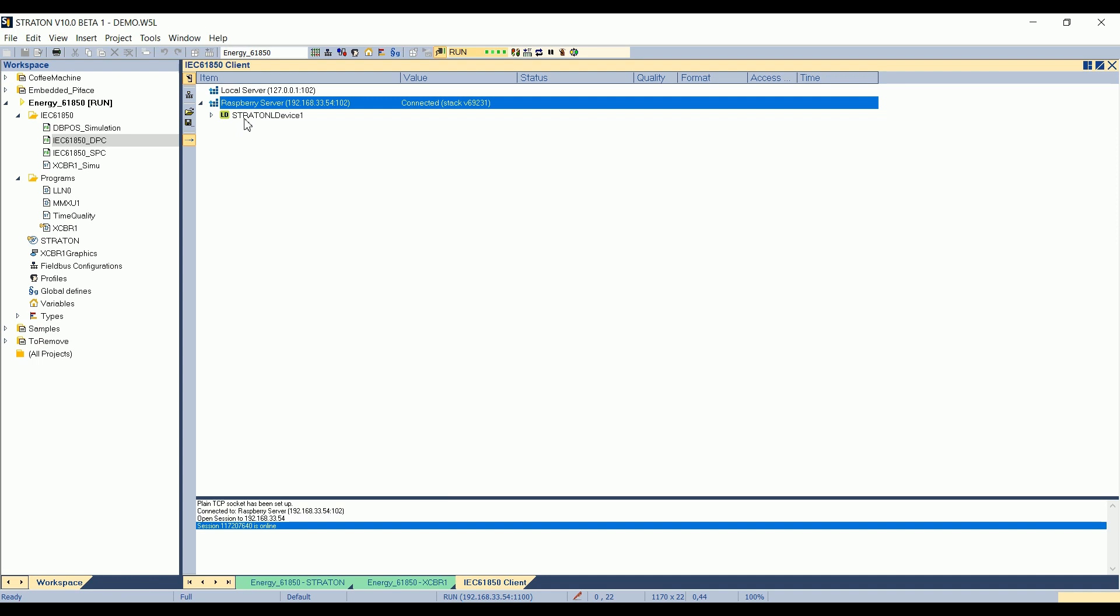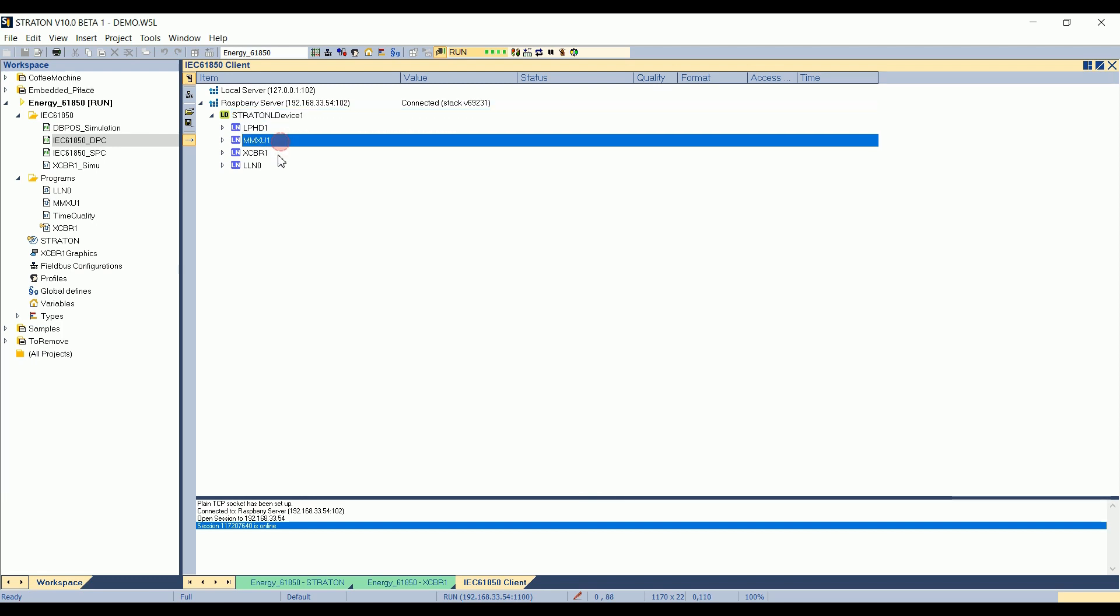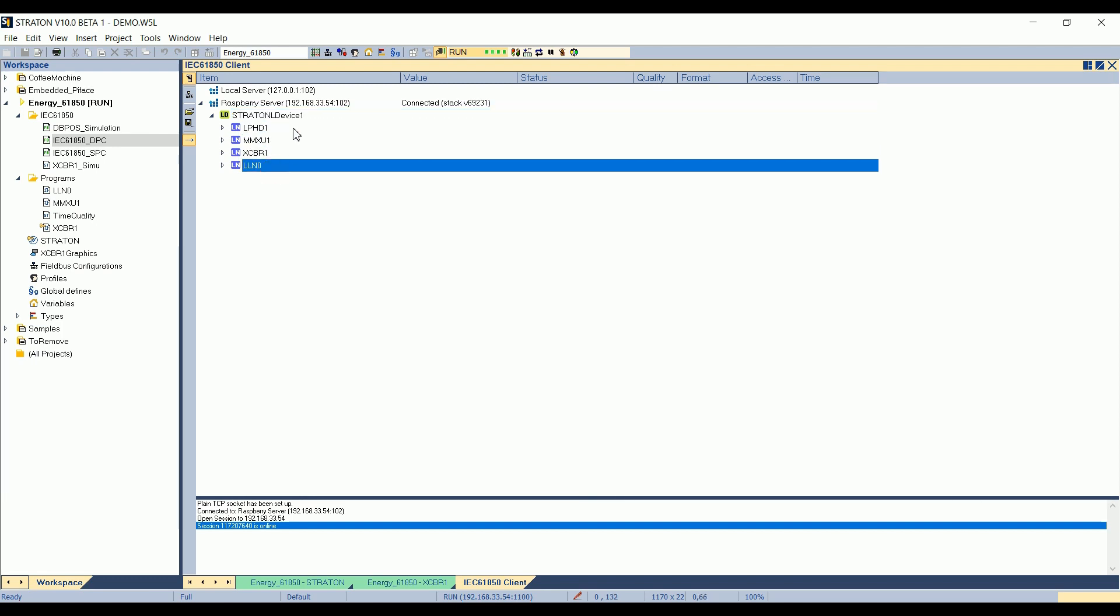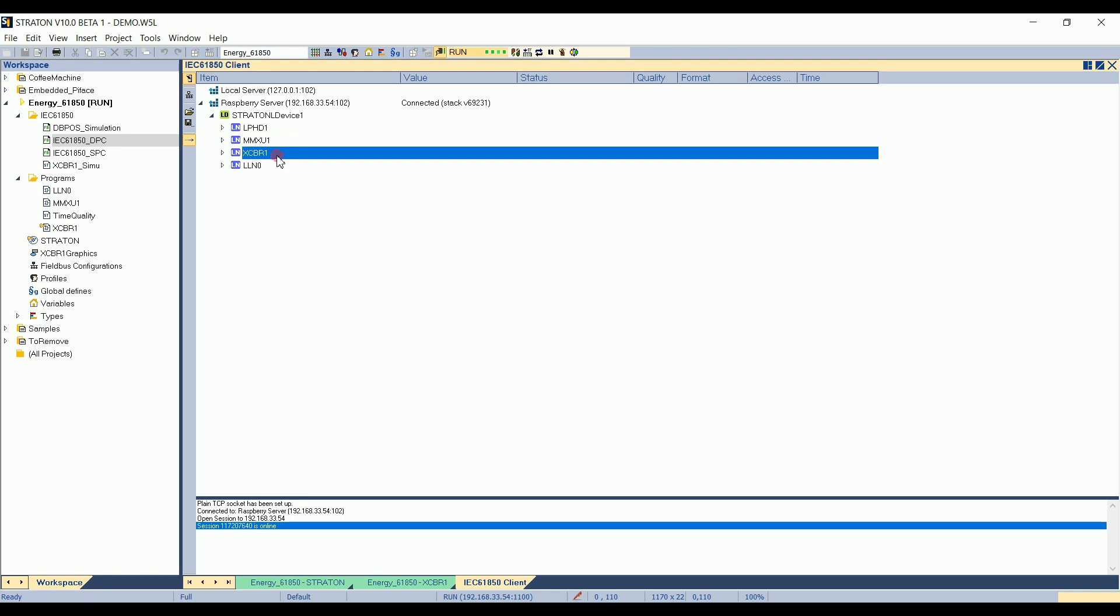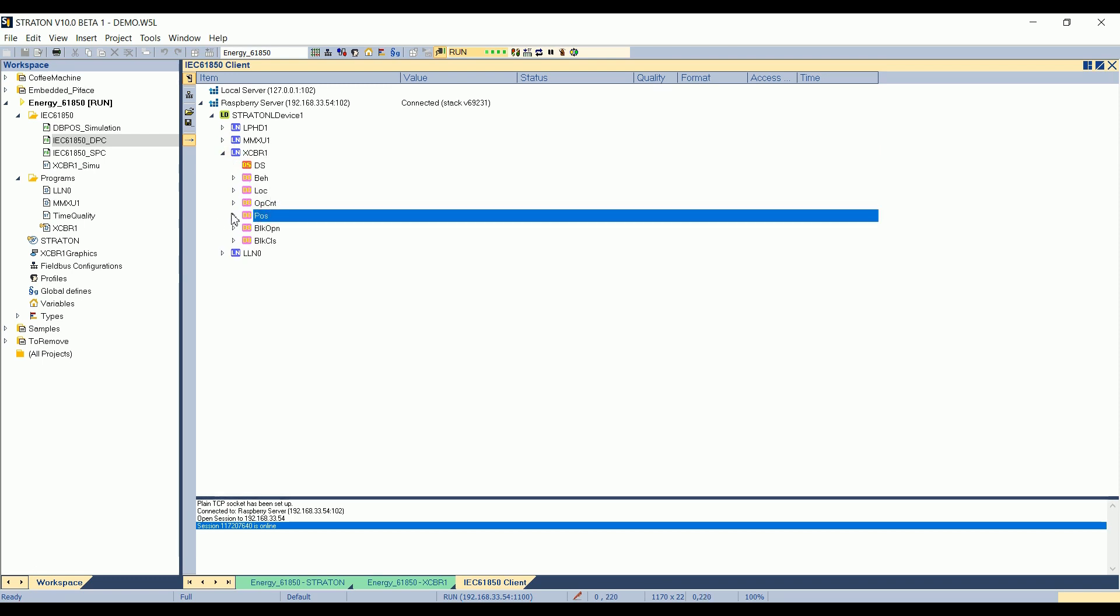It connects to the logical device, so to the Raspberry which is running the 850 server. And I can see my four logical nodes: LLN0, LPHD, MMXU, and the circuit breaker. If I expand the circuit breaker, here I can see the position, for example, the data object position with the data attributes. For example, the control model here, which is equal to 4 on the server side.